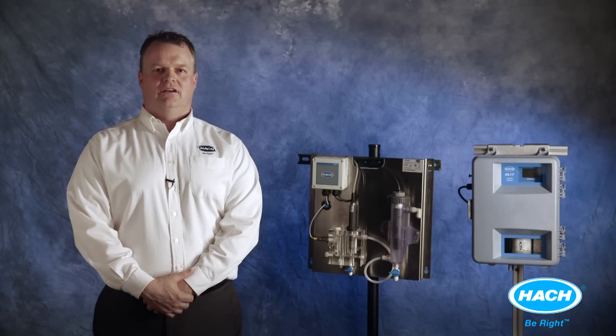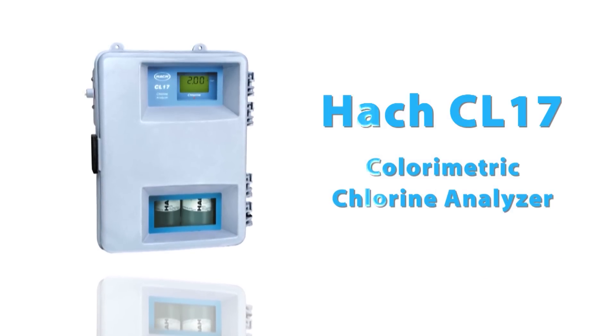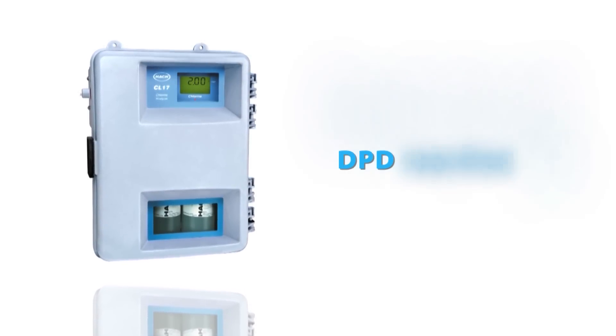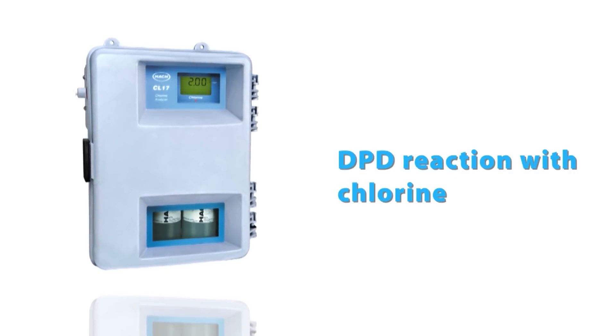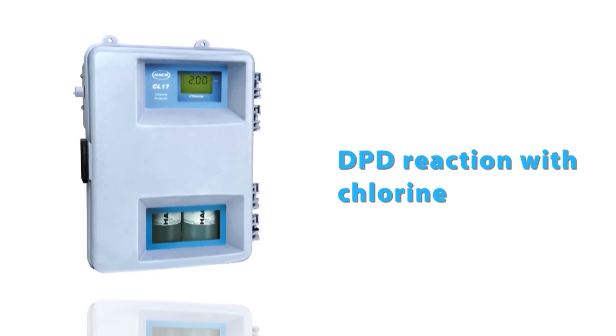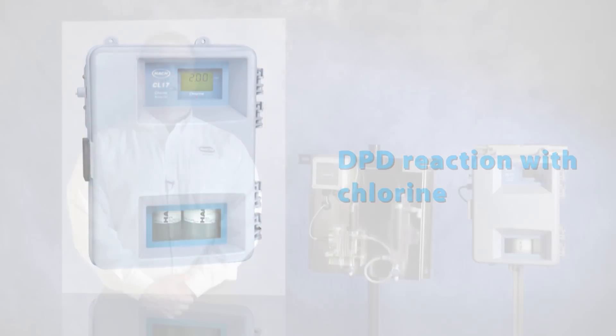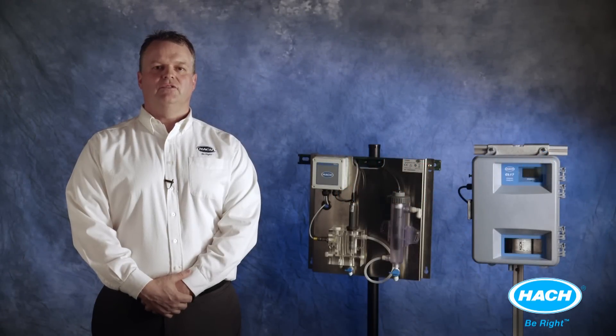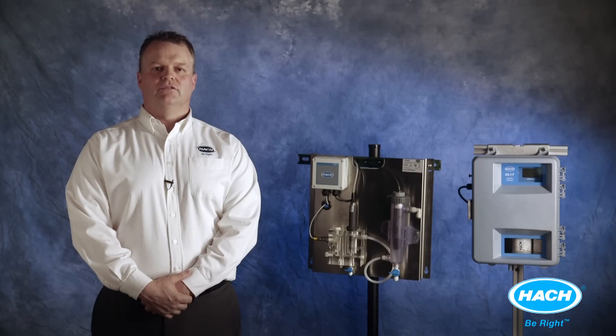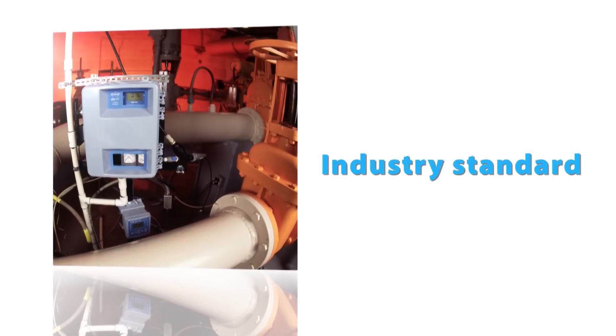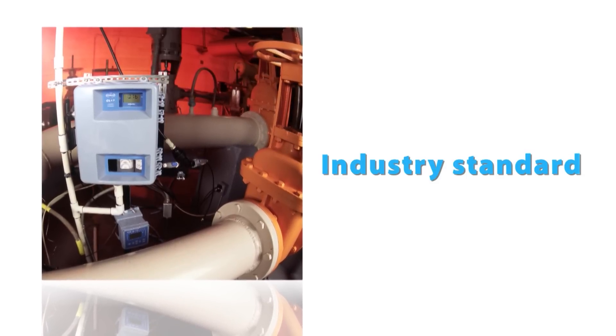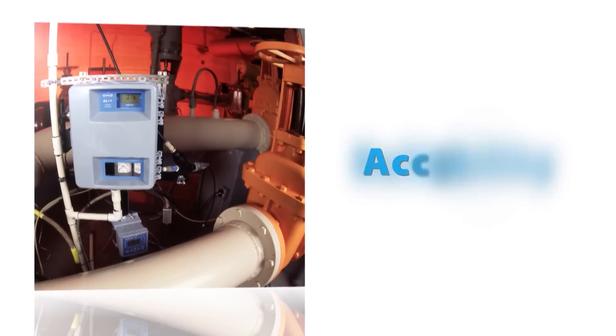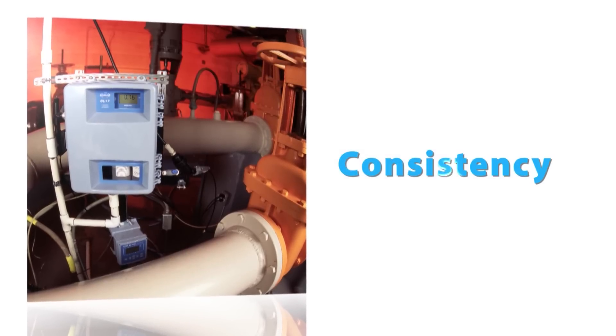In addition to the CL10, Hach also offers the CL17, which is a colorimetric chlorine analyzer. This technology uses a detection method based on DPD reaction with chlorine, which forms a magenta color with intensity proportional to the chlorine concentration. The DPD method has been approved by the US EPA for online analysis of chlorine residual for over 30 years. It is the most widely used and trusted chlorine reference method in the world. The Hach CL17 is the industry standard in colorimetric chlorine analysis and is well known for its accuracy, reliability, and consistency with lab and field methods.